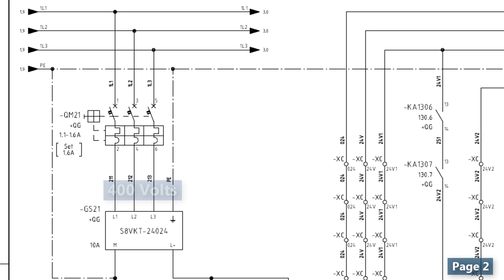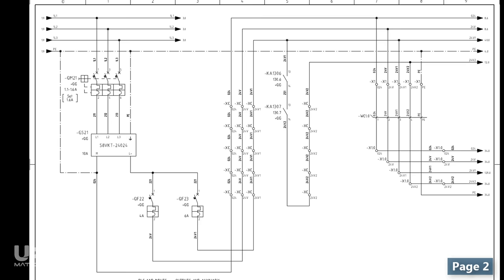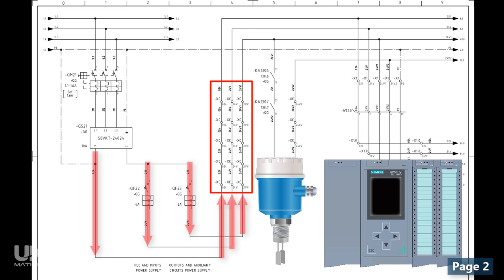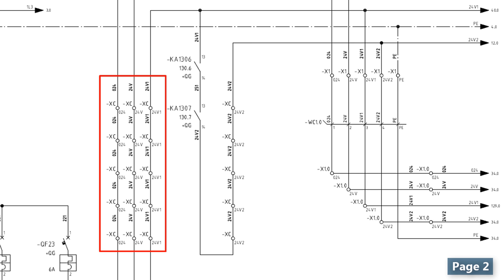On page 2, the mains power source is feeding a 24V power supply and it provides us with a voltage of 24V with 10A of capacity. From there, we have extended this voltage using some terminal blocks so that we can deliver the power to different instruments, PLC cards, PLC CPU or whatever device which needs 24V to power on. But wait, this part of the drawing seems a little bit strange as all of these terminals have the same tag of XC.